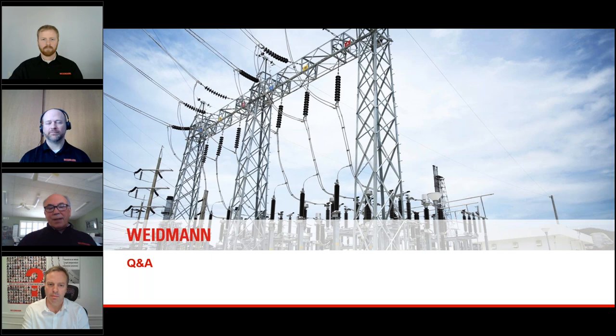Our industry is fairly slow moving. This methanol measurement has been around for more than 20 years, but in the transformer industry, I would call it in its infancy. So there's a lot of research, most of it coming out of Hydro-Quebec and IREQ, which is their research facility. But I know of two labs anyways in the US that can measure methanol and give you an estimation of paper degradation.